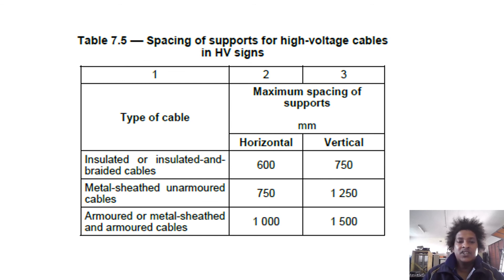For insulated or insulated-and-braided cables, the maximum spacing is 600 mm horizontal and 750 mm vertical. For metal-sheathed unarmoured cables, the spacing is 750 mm horizontal and 1250 mm vertical. For armored or metal-sheathed-and-armored cables, the spacing is 1000 mm horizontal and 1500 mm vertical.